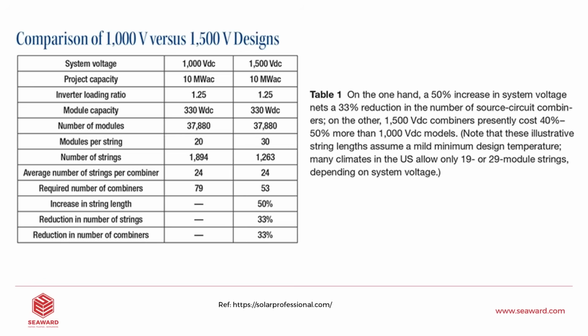So a quick comparison here of the differences between 1000 volt and 1500 volt systems. And this is taken from a great website, solarprofessional.com. And you can see that on the one hand, a 50% increase in system voltage nets us a 33% reduction in the number of source circuit combiners. On the other, 1500 volt combiners presently cost 40 to 50% more than 1000 volt combiners. So actually the price of a 1500 volt combiner is more than a 1000 volt combiner.